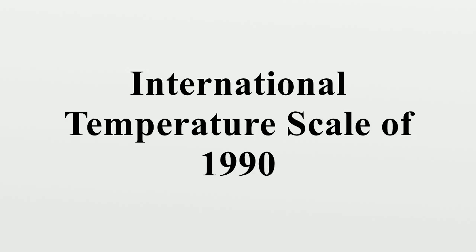ITS-90 also draws a distinction between freezing and melting points. The distinction depends on whether heat is going into or out of the sample when the measurement is made. Only gallium is measured while melting; all other metals are measured while the samples are freezing. A practical effect of ITS-90 is that triple points and the freezing and melting points of its 13 chemical elements are precisely known. Only the triple point of Vienna Standard Mean Ocean Water is known with absolute precision, regardless of the calibration standard employed, because the very definitions of both the Kelvin and Celsius scales are fixed by international agreement based, in part, on this point.